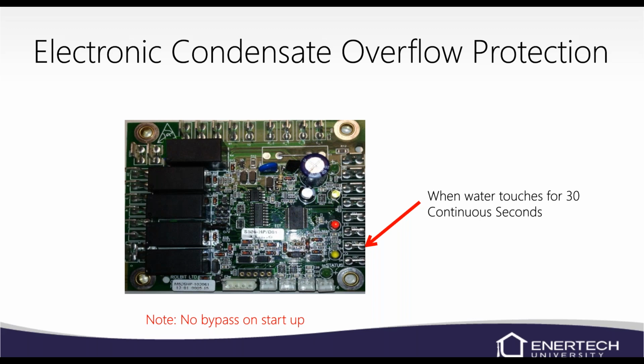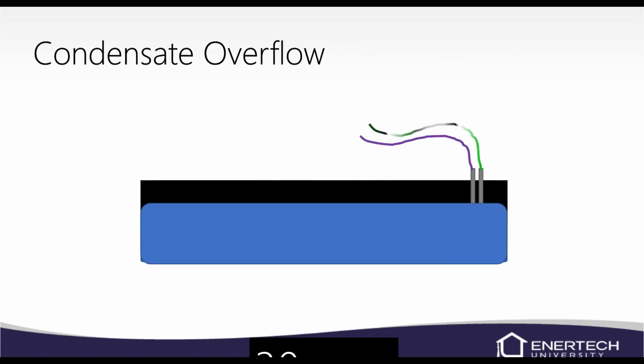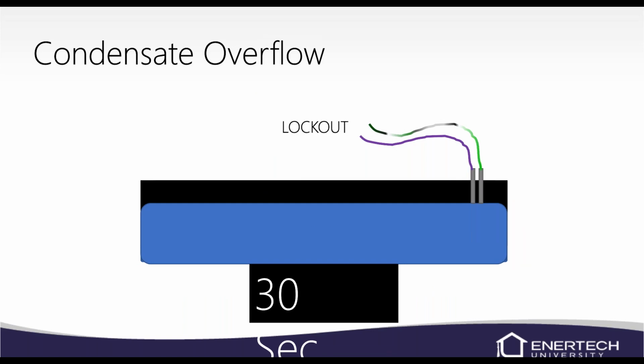If you pull one of these wires off the board, and it still locks out on condensate overflow, then we know we've got a problem with the board itself. Highly unlikely, but it's an easy way to check whether it's a wire issue or a board problem. Just take one of the wires off, and it shouldn't ever be able to lock out. Basically, the water here just completes that circuit of the, actually it's a purple and a green/black stripe wire, the other wire.